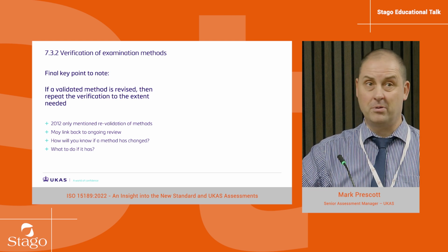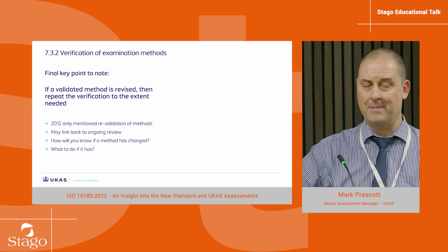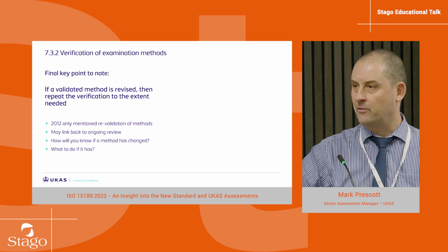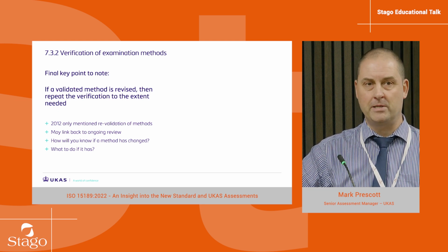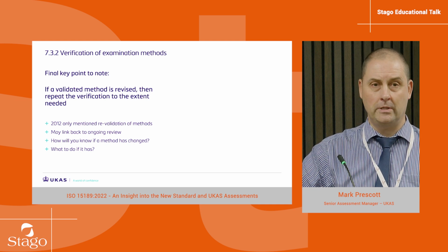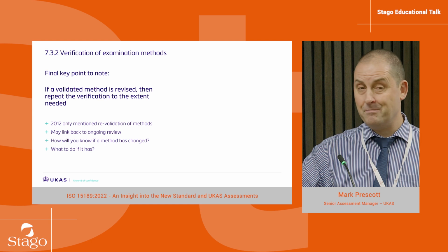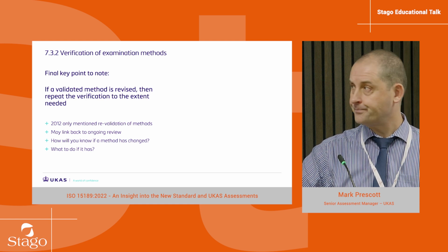So for example, a reference range might change, or a sample type might change. I've seen things like lateral flow assays where they say add 3 drops, and then you get the next kit insert and it says add 4 drops. They've changed it, so you need to re-verify it at that point because it's not what it was before. I've seen many labs miss that sort of thing.